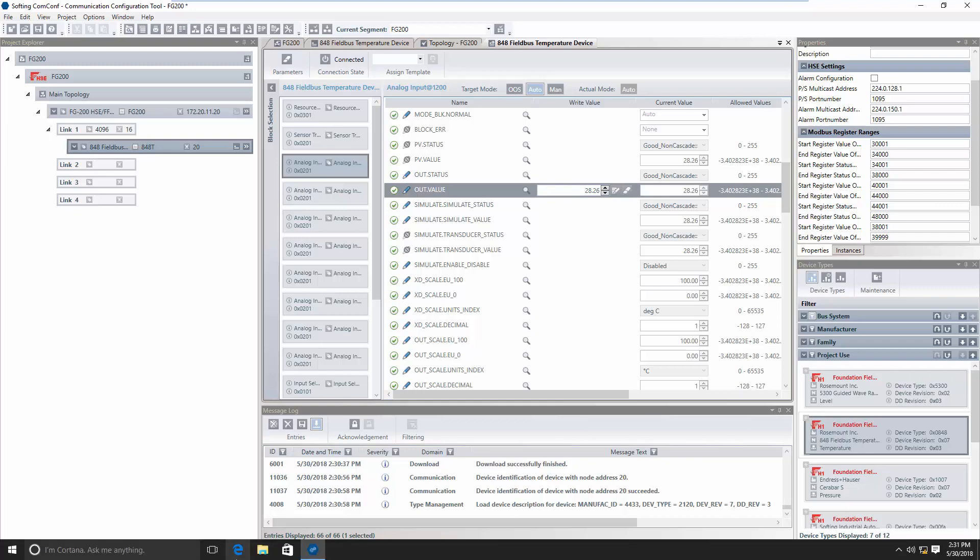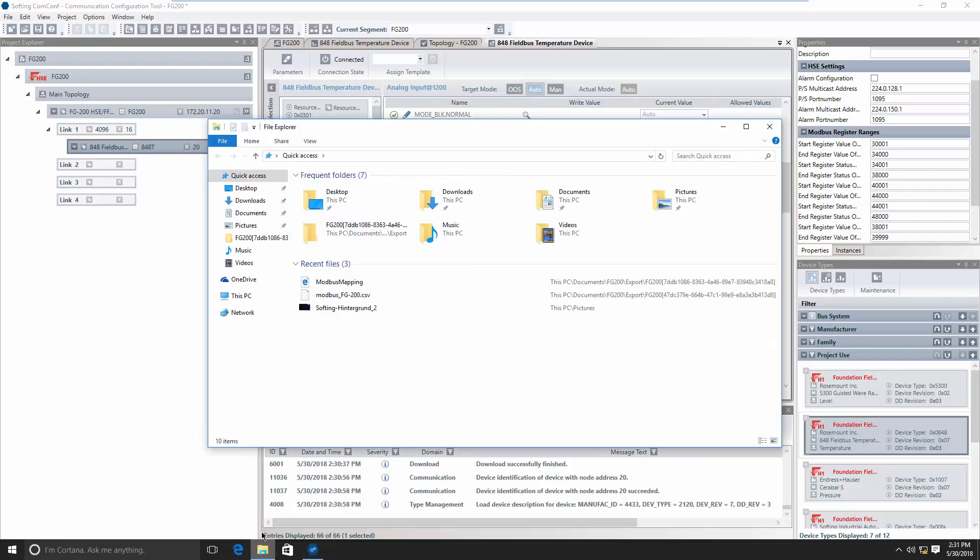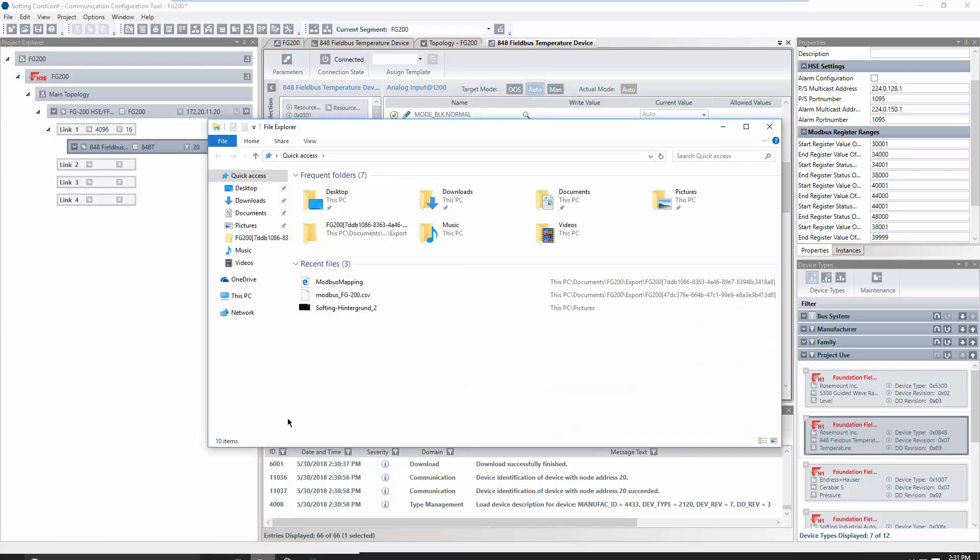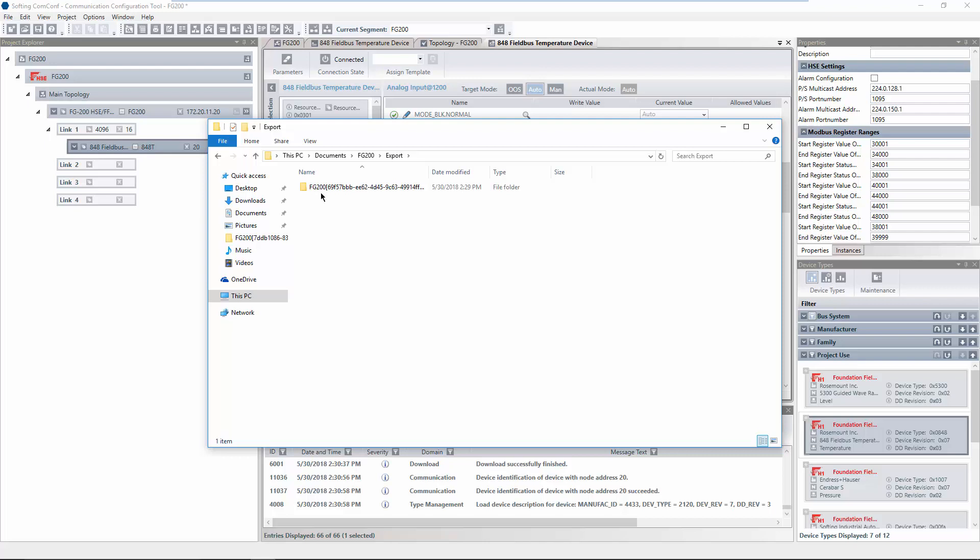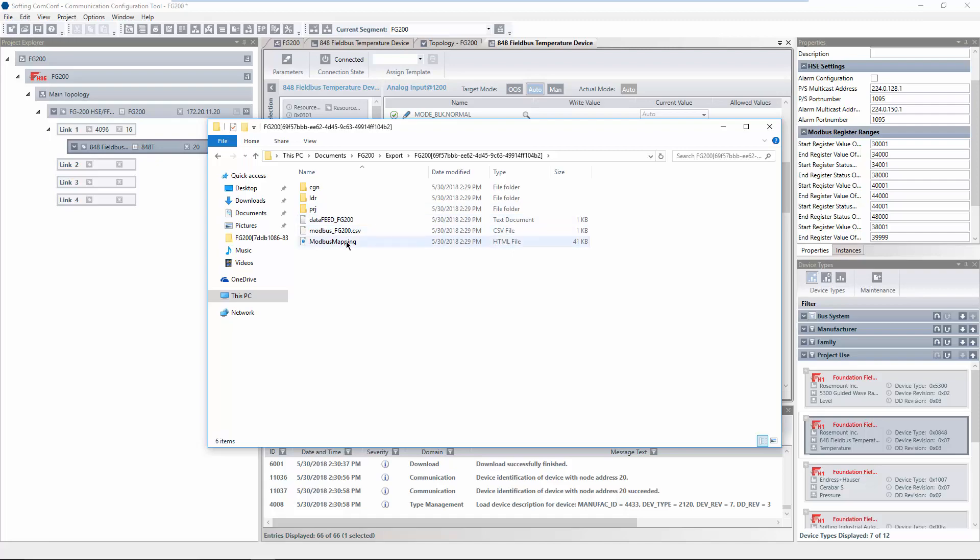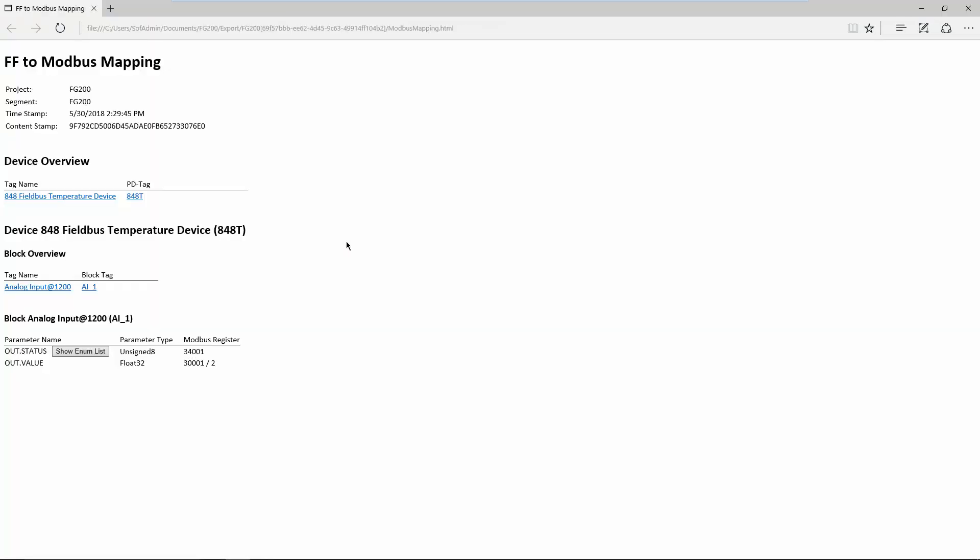Open the Windows File Explorer and navigate to the folder containing your project. Open Subfolder Export. When a segment is built, a subfolder for the segment is created. Open the subfolder and open the file Modbus Mapping. In this HTML file, the mapping of the parameters and the Modbus register is shown. The number 2 specifies that the value of OutValue consists of two Modbus registers.